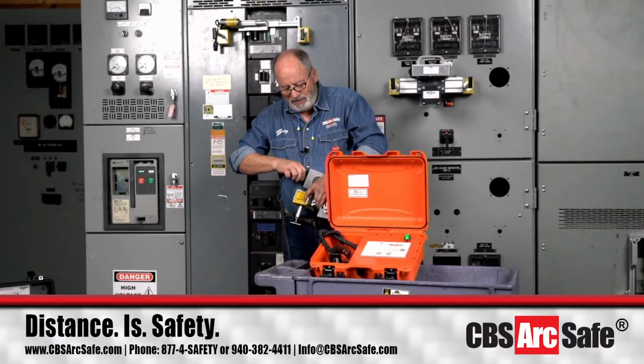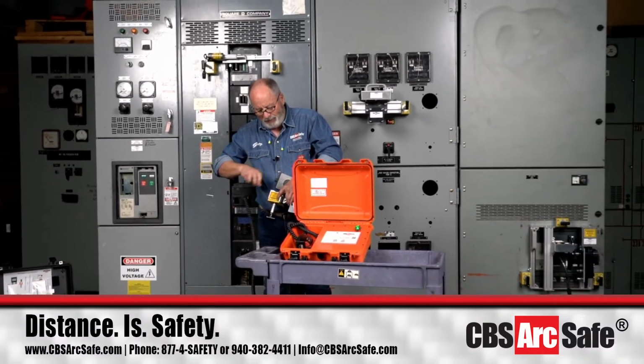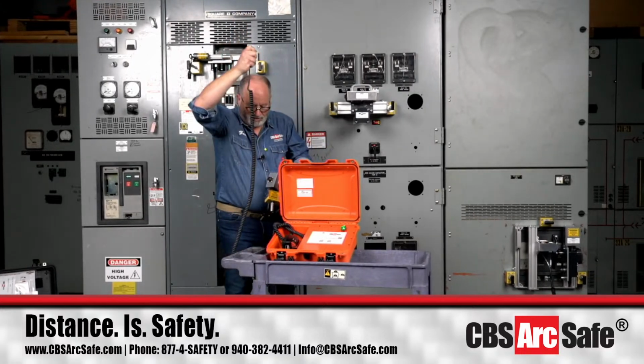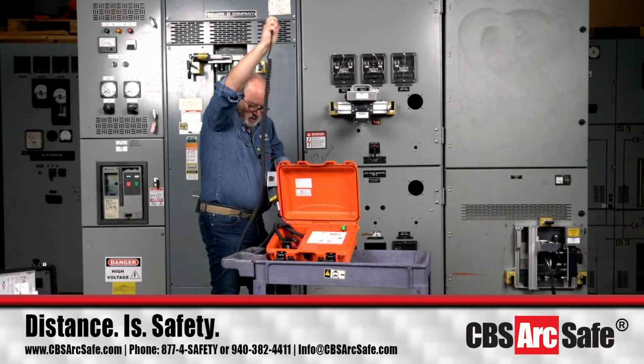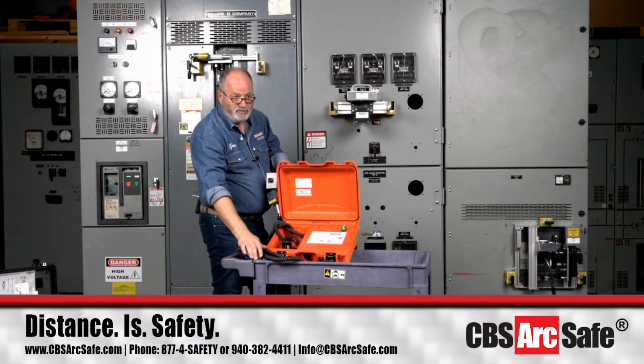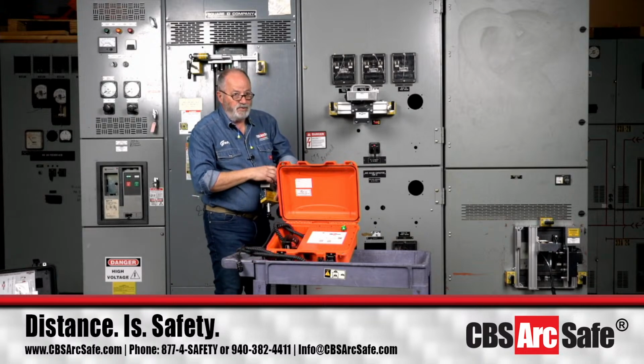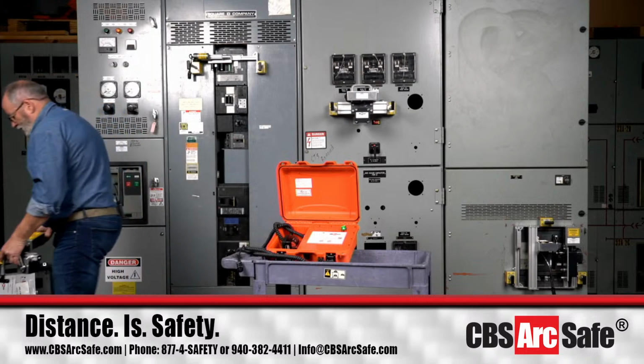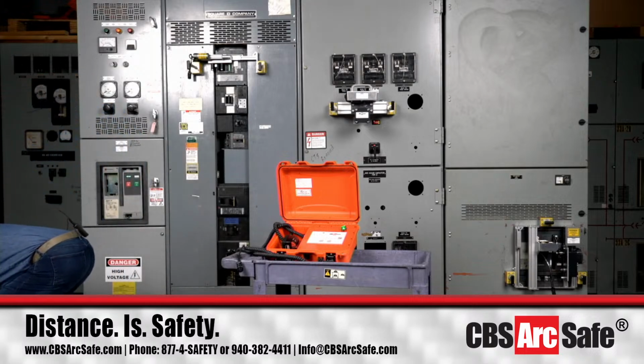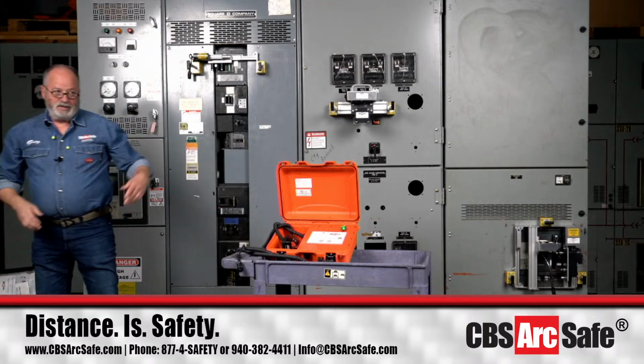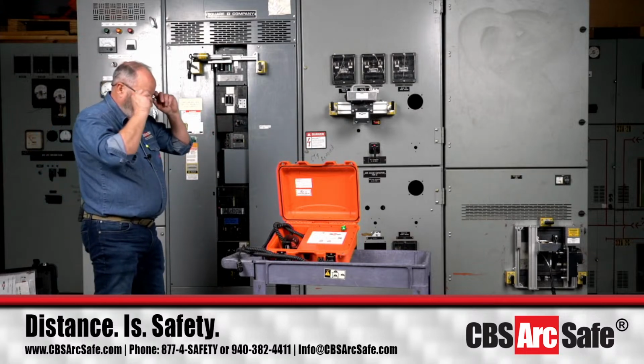Now, in a lot of data centers, you'll see, especially newer things, a vacuum breaker at each end, usually like 15 kV, with a knife blade switch, and then your low voltage 5,000 amp mains on a main-tie-main setup, okay?